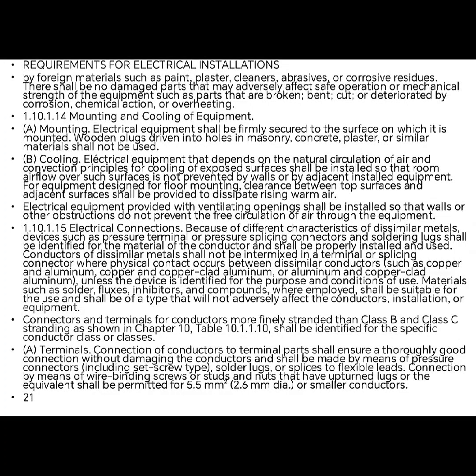Contamination by foreign materials such as paint, plaster, cleaners, abrasives, or corrosive residues. There shall be no damaged parts that may adversely affect safe operation or mechanical strength of the equipment, such as parts that are broken, bent, cut, or deteriorated by corrosion, chemical action, or overheating.